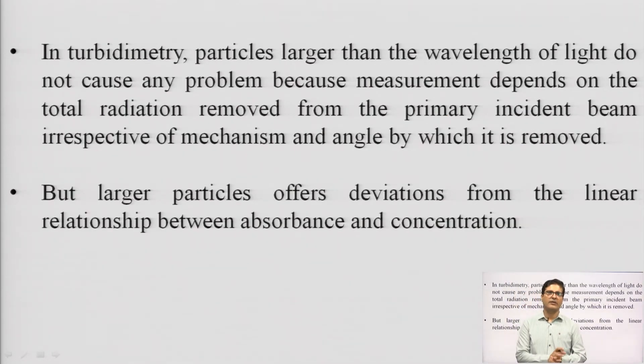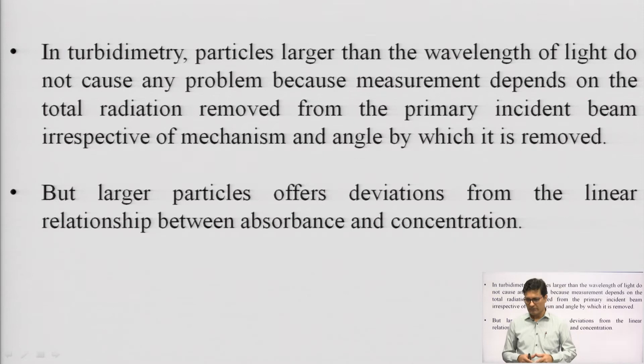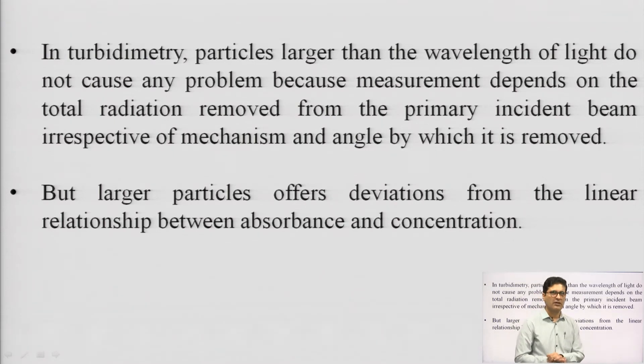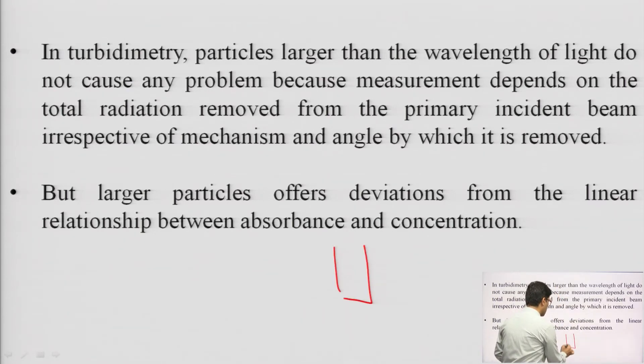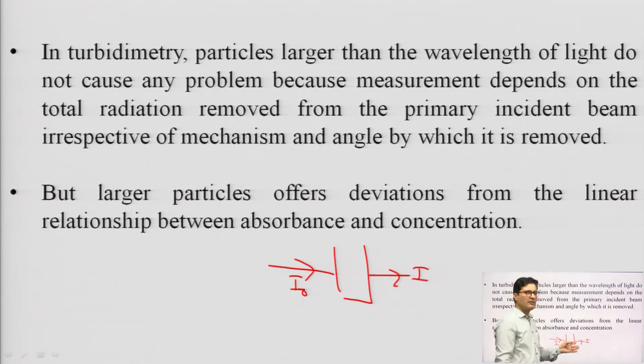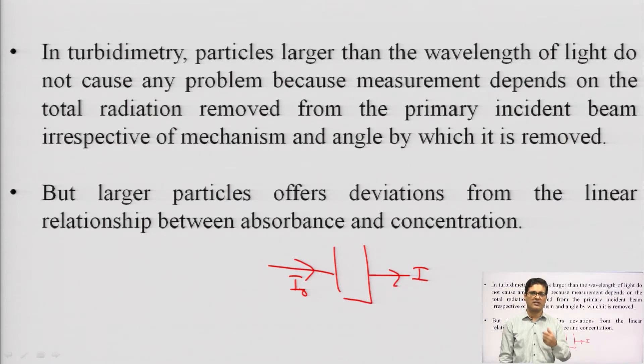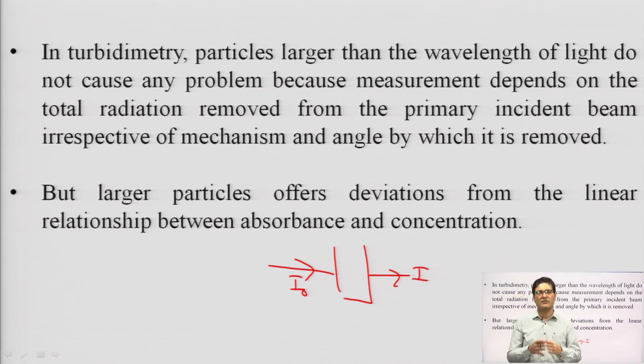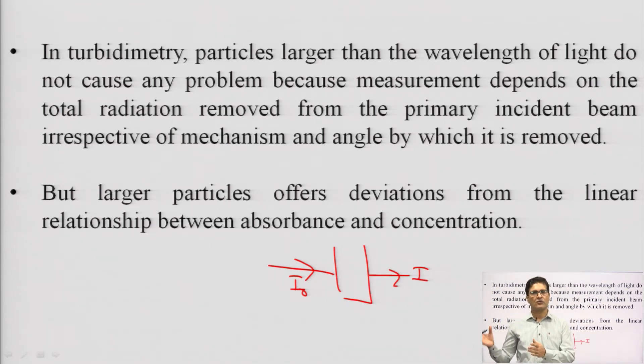In turbidimetry, particles larger than the wavelength of light generally do not cause any problem, because the measurement depends upon the total radiation removed from the primary incident beam, irrespective of the mechanism and the angle at which it is removed. We only need to see how much intensity is being lost — whether due to absorption, reflection, or scattering — and compare incident light intensity to transmitted light intensity.